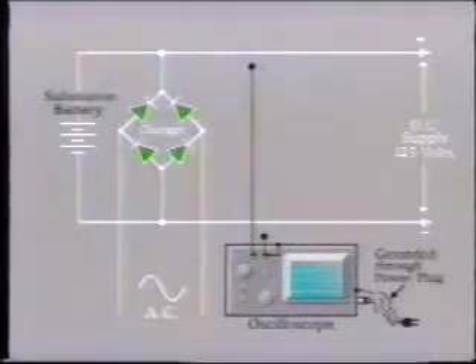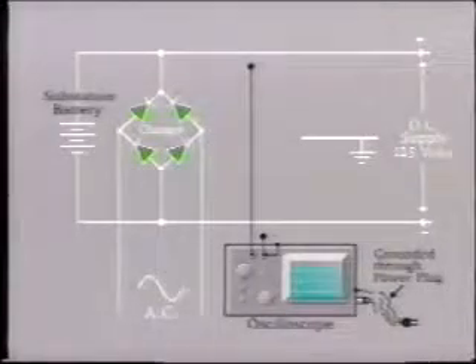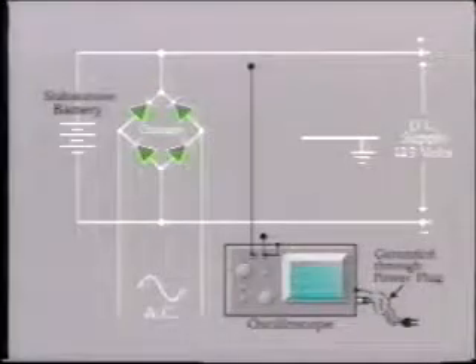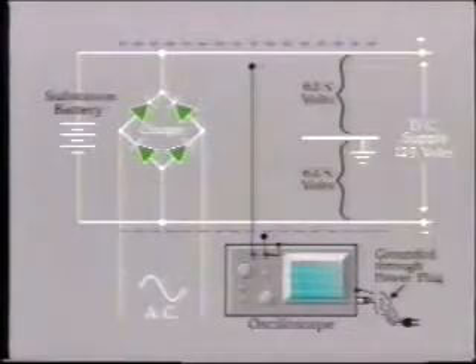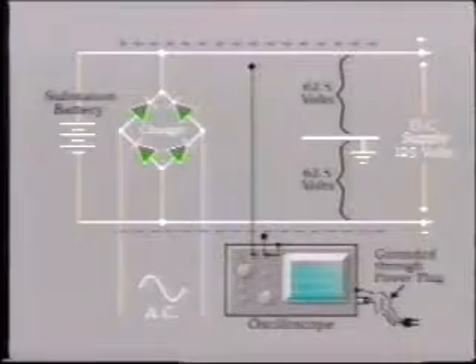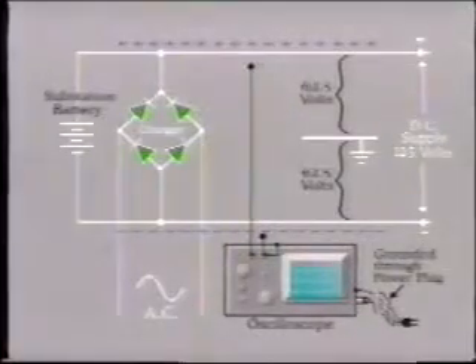Well, substation batteries and telephone circuits as well are deliberately isolated from ground. So the capacitance between the DC cables and ground cause ground to be at a potential halfway between the positive and negative feeds, say 62.5 volts DC.